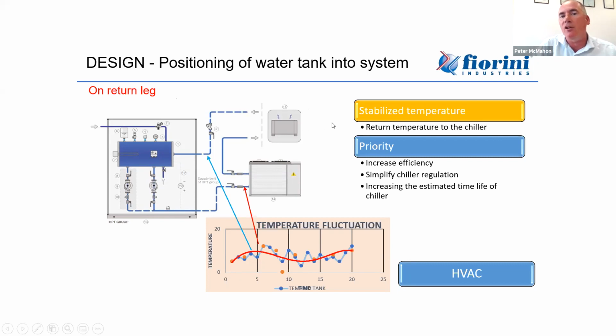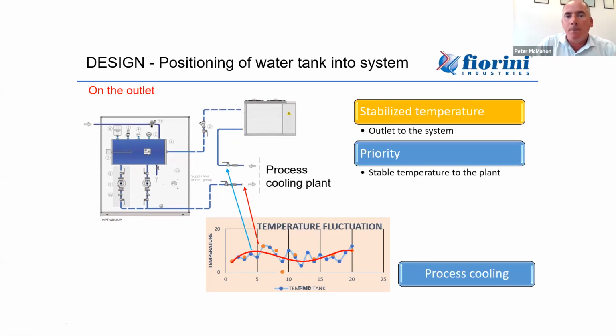That can be fan coil units, it could be a cooling coil in a mushroom form or whatever, it doesn't really matter. On the return, we have the water coming back. So where we may have fluctuations in load, that's going through a buffer tank, which is obviously stabilizing the temperature. So we get a very stable temperature coming out of that buffer tank back to the chiller. So you can see here on the red line, nice stable temperature, which is very, very good for your piece of kit that you've invested a lot of money in.